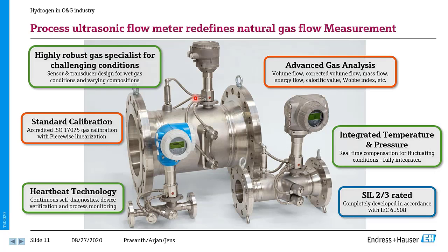One of the unique features of this device, based on the biggest challenge the process industry is facing, is the ability to measure wet gas conditions. In a gas line, roughly around 5 to 6% liquid volume fraction, this device works quite well, and this is made possible because of the advancements which we made on the sensor design as well as in terms of the signal processing. In terms of the calibration of this device, these devices will be calibrated in an ISO 17025 gas calibration rig in our facility in Switzerland. And last but not the least, these devices are equipped with Heartbeat Technology.